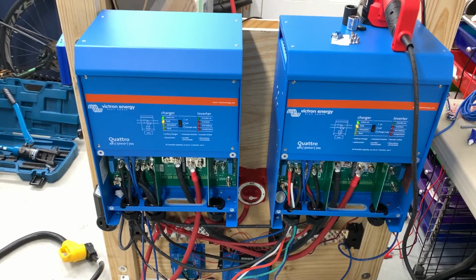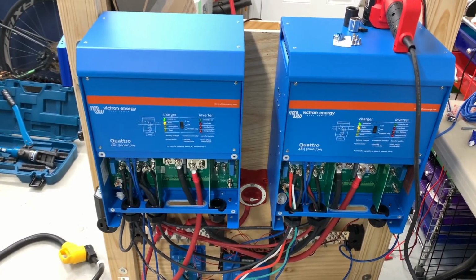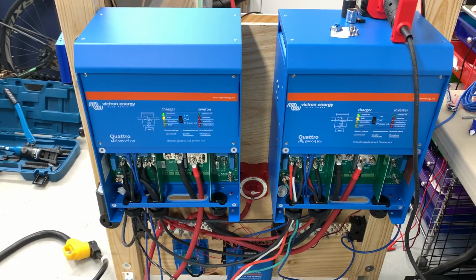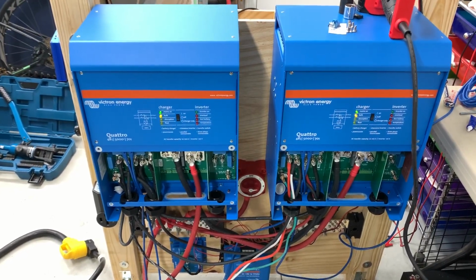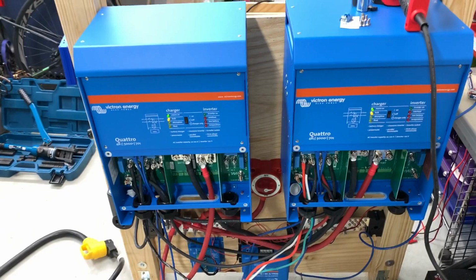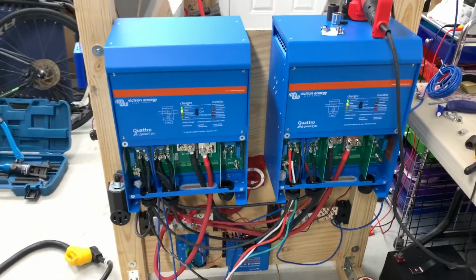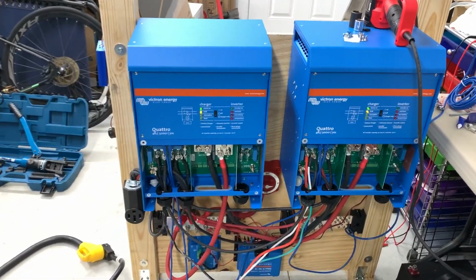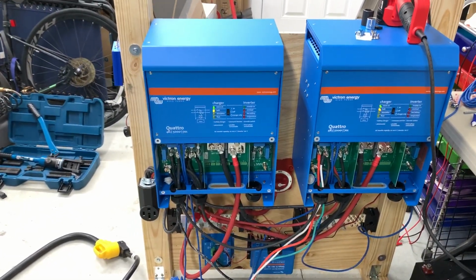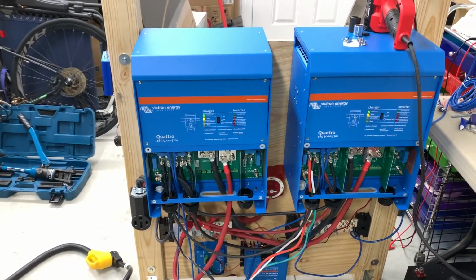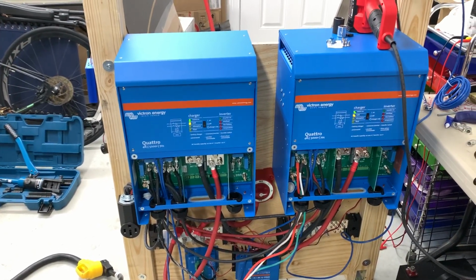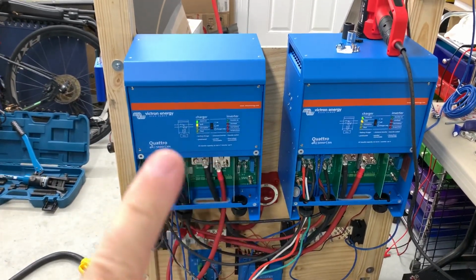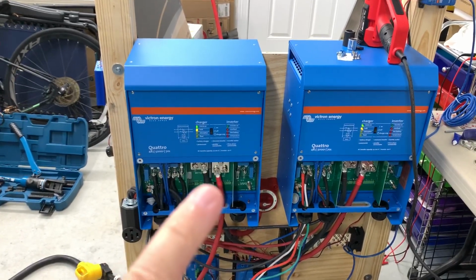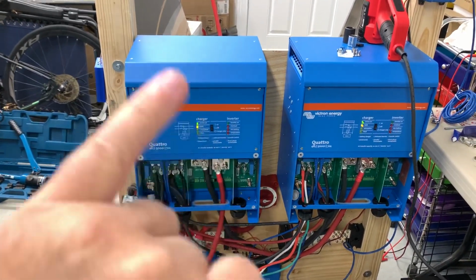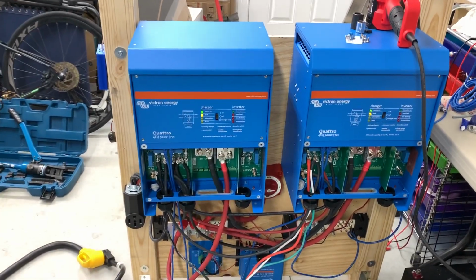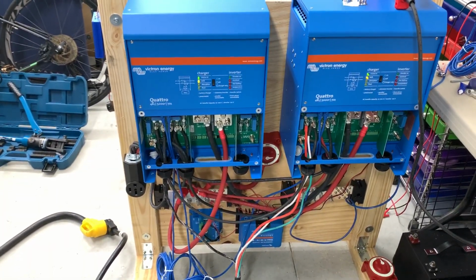I might have to go the old school route with an actual relay or DC contactor as opposed to a solid state contactor. The disadvantage is you also have to include a pre-charge delay circuit, so I'd have to get Chargery's pre-charge delay board, which turns on a smaller relay that goes through a resistor and slowly charges up the capacitive circuits here, then turns on the main relay. So we'll play with that.